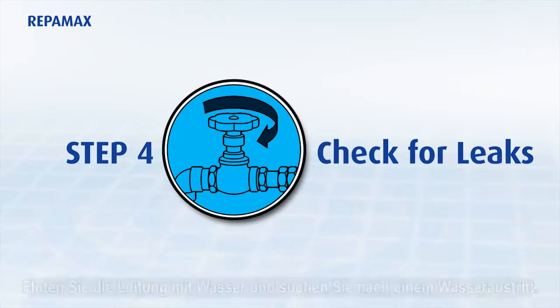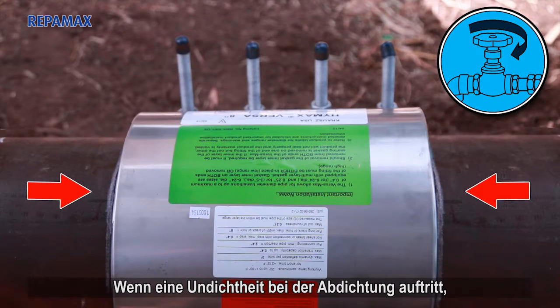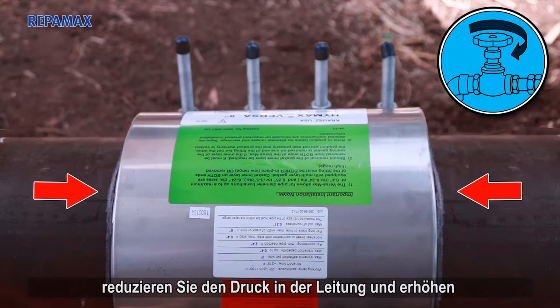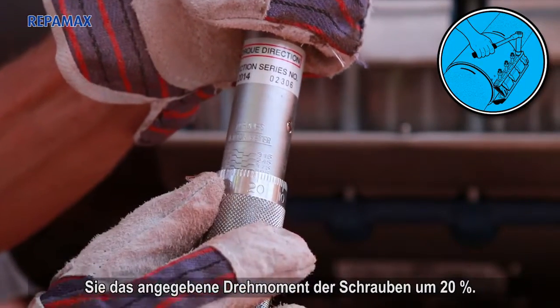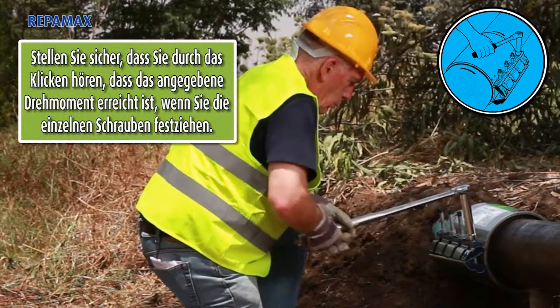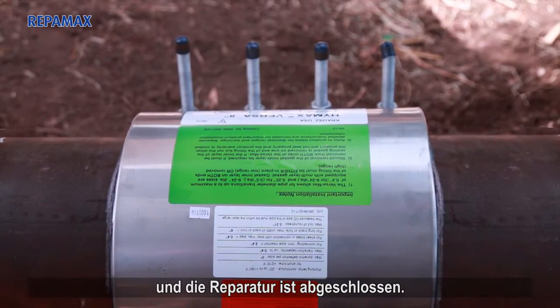Step 4: Recharge the line and check for leaks. If any leakage across the seal end is evident, reduce the pressure in the line and increase the labeled torque of the bolts by 20%. The REPAMAX is now installed and the repair is completed.